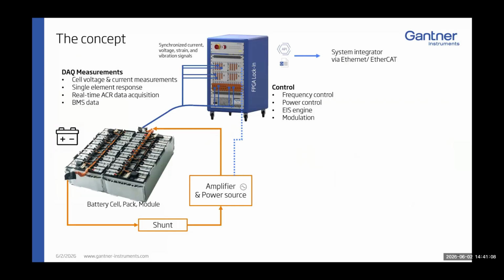That's the system setup — we'll have a live demo later where you can watch everything live. In short, we have our data acquisition cabinet connected to the device under test, which is a battery. For each cell we measure the voltage, and with a shunt or another measurement device, like from LEM or DaniSense with a current transducer, we measure the overall current flowing through all the cells. Then we have a power source able to charge or discharge the battery.